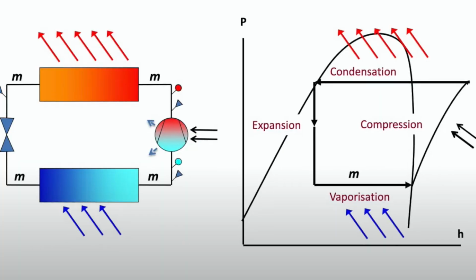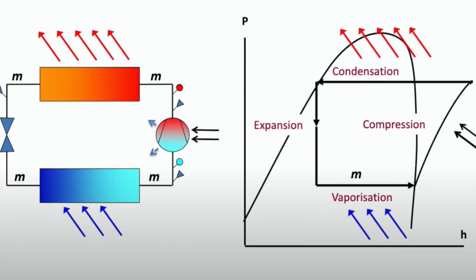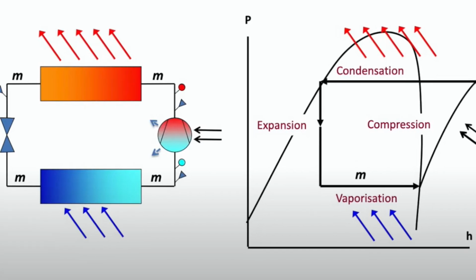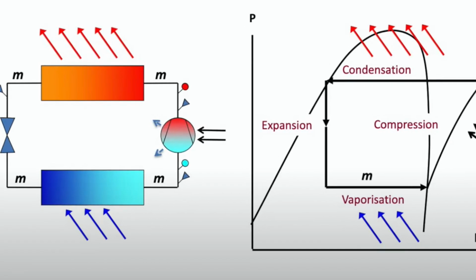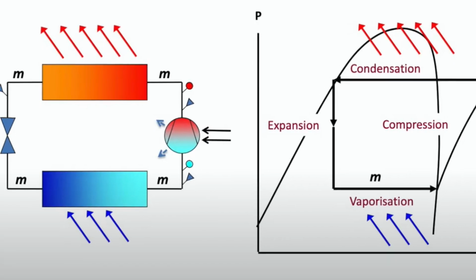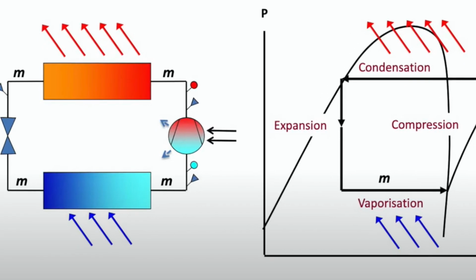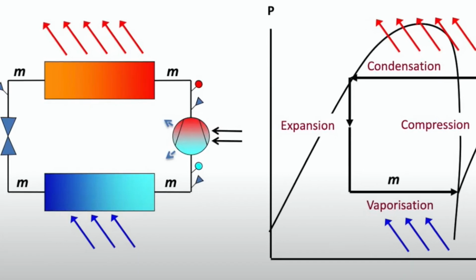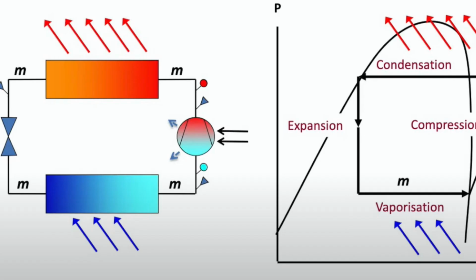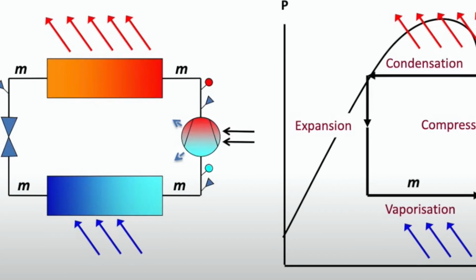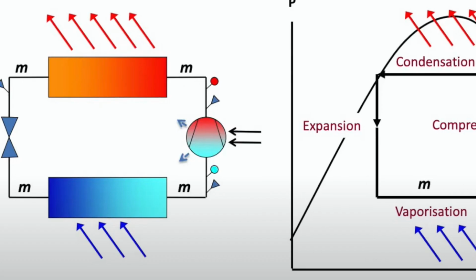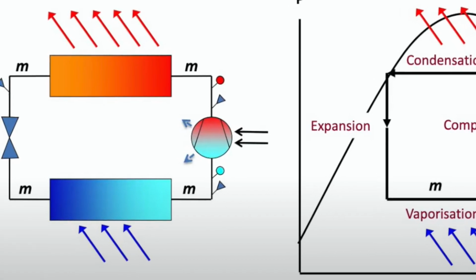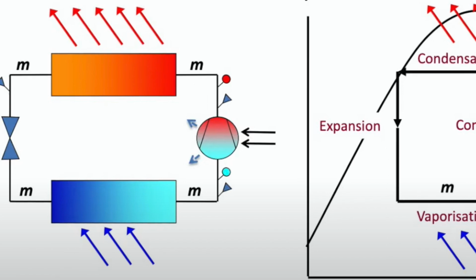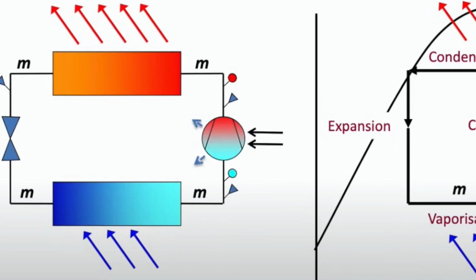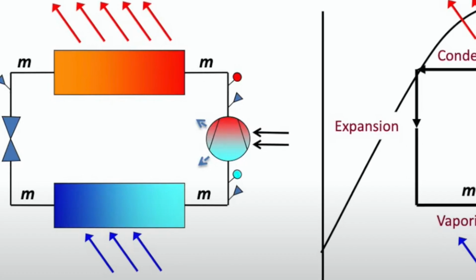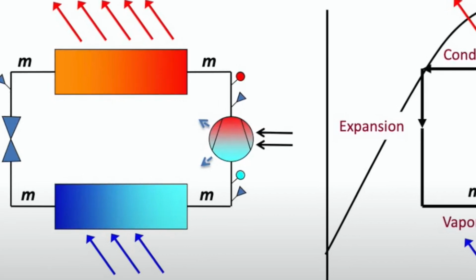Here we're looking at two diagrams. On the left side, we start with the compressor on the centre right, showing electrical input via the black arrows. Temperature and pressure up to the condenser, showing heat being rejected to the atmosphere, and in it the refrigerant changes state from a vapour to a liquid. It's then fed to the expansion valve. Then through the expansion valve it vaporizes into the evaporator, where you can see by the blue arrows heat being absorbed from the conditioned space or cooling process before the vapor refrigerant goes back to the compressor to start the cycle again.